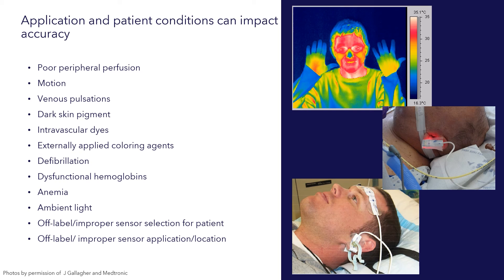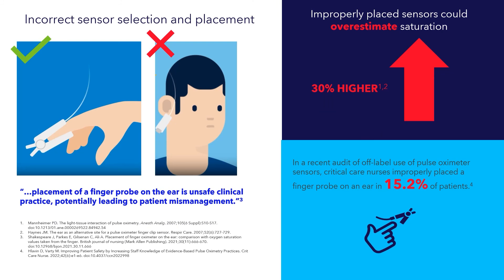Incorrect sensor selection and placement has significant patient safety implications. Often the use of a finger sensor on the ear or forehead can result in erroneously high or overestimation of oxygen saturation, especially in the face of desaturation. So it's important to use the right sensor for the right patient in the right location.